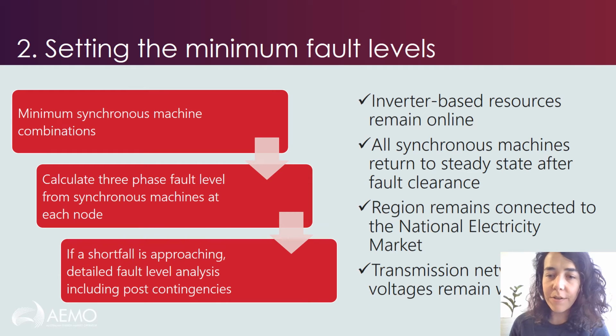Taking that understanding of the nodes and projections for minimum synchronous machine combinations, we calculate the three-phase fault level at each of the nodes that we've selected. And if we're concerned that there is a shortfall approaching, we also do detailed electromagnetic transient analysis using PSCAD in order to understand the full detail of the fault level requirements at that level. I've also listed down the right-hand side of the slide the success criteria that we use when we're deciding whether or not a minimum fault level amount at a node is sufficient and we can consider it to be a steady state that we can plan to.